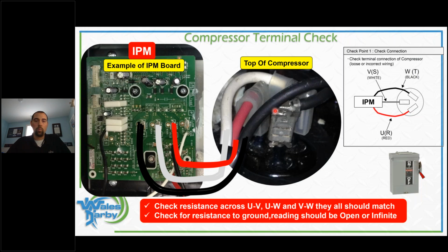We need to disconnect those wires at the compressor. Make sure there's no added resistance there, or maybe shorts from wires that are giving us false readings. So disconnect those terminals. Take a picture before you do so. You know, obviously, disconnects off there on the right-hand side.